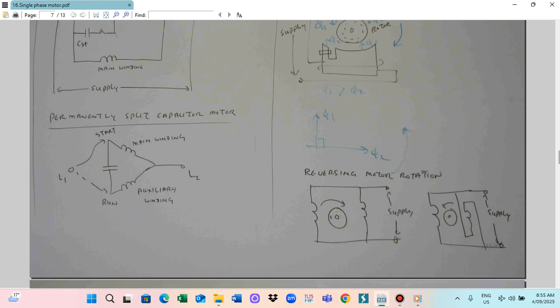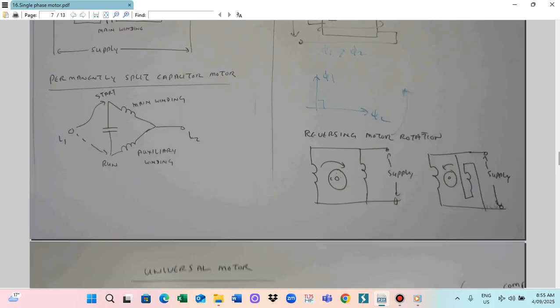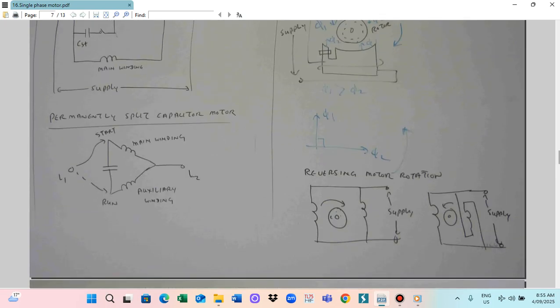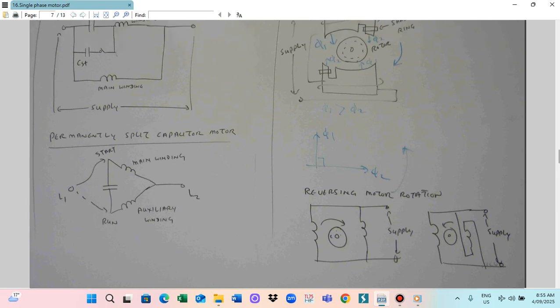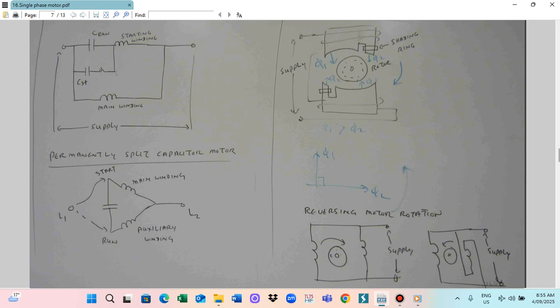So if you want to reverse the three-phase motor, you have to change one phase connection. Line 1 is connected to line 2 and line 2 connected to line 1, so the motor direction will be changed. For the single-phase motor, if you want to change direction, you have to change the connection of the starting winding. By reversing the starting winding, the motor will reverse. So this is for reversing the rotation. The shaded pole motor you cannot reverse easily because the shaded pole is permanently fixed.